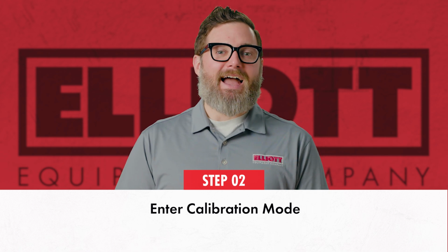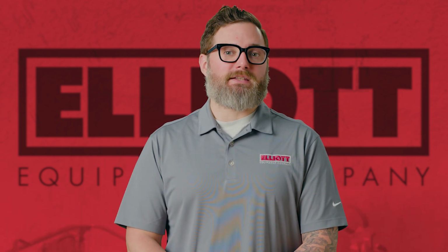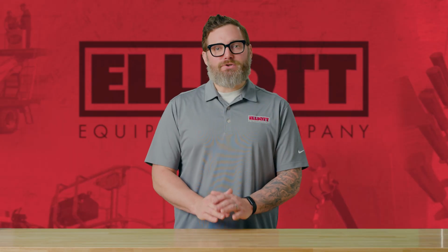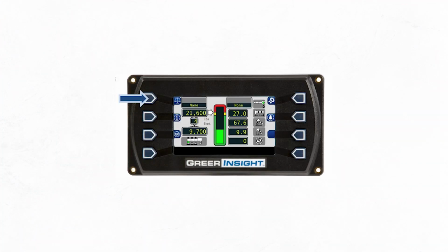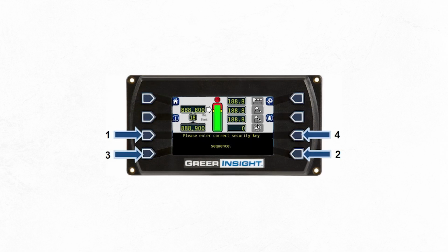To do this, the actual crane setup must be reflected on the display. Now, to enter calibration mode, you need the display to be in normal operating mode. Then press the calibration button if you can see it on the screen. The icon will be scales. The display should prompt you for the security code. You're going to need to enter the security key sequence within 5 seconds or the system will revert to the normal operating mode. You can see the sequence order here.